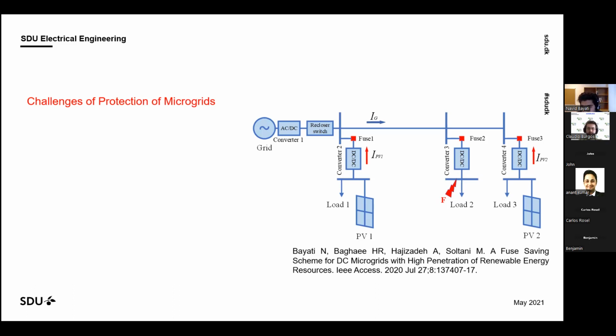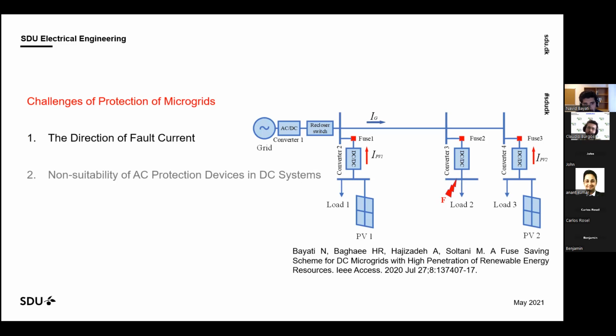The problem is that if, for example, we have a fault at F, in load 2, then the fault current comes from the grid, PV1 and PV2. So we have different fault currents coming from different sides of the grid to the faulty point. But if we have one sensor, for example, in converter number 1, we can only sense the current coming from the grid. So we cannot find anything relating to PV1 and PV2. So normally in this system, we should have sensors everywhere.